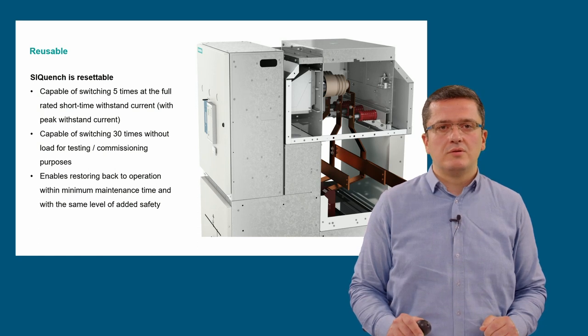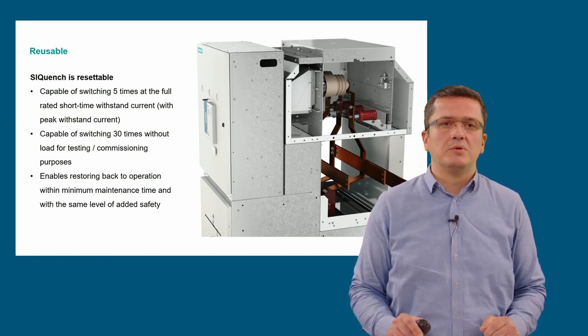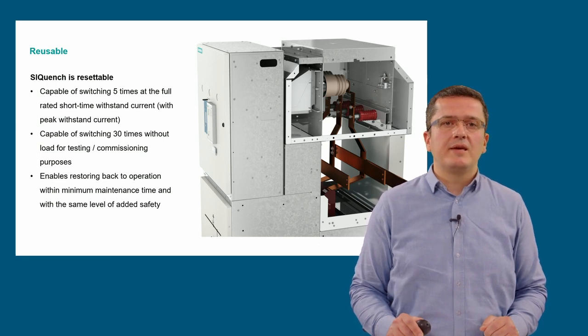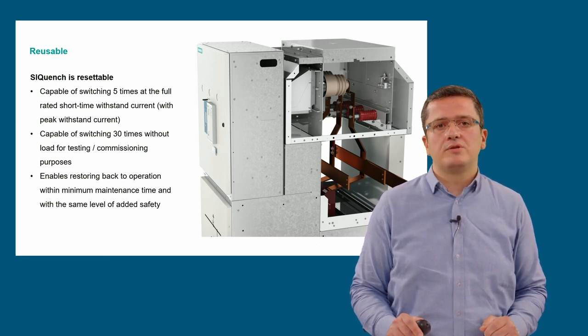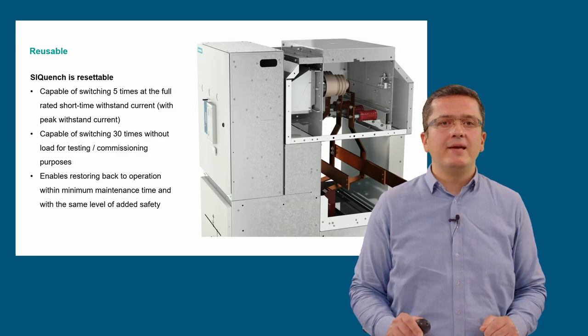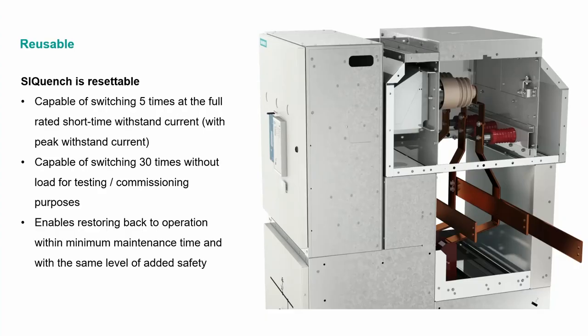SIQuench has a unique feature. It is reusable or we can call it as resettable. Resetting is done from front of the panel without the need for opening any covers or even any doors. It can withstand five consecutive switching operations with the full rated short time withstand current of the switchgear. It also allows for 30 real physical switching operations without load for testing and commissioning purposes.